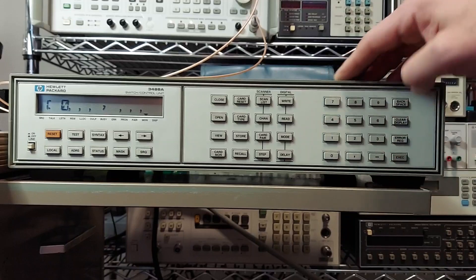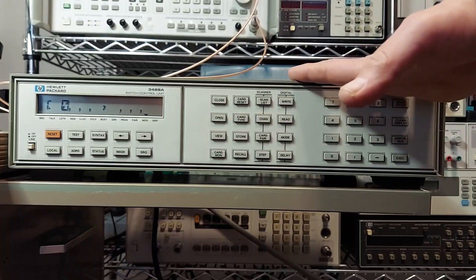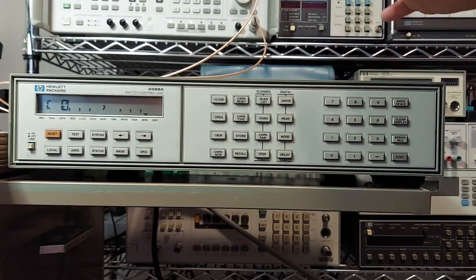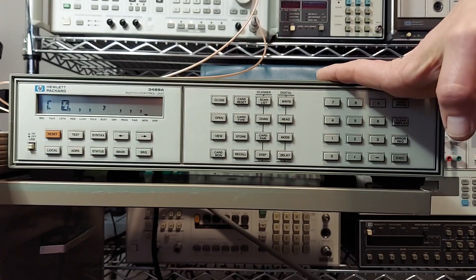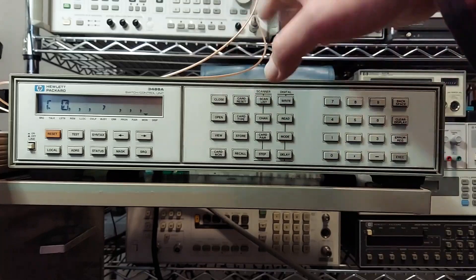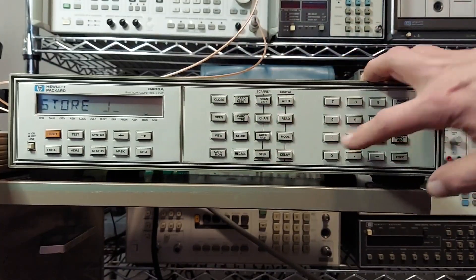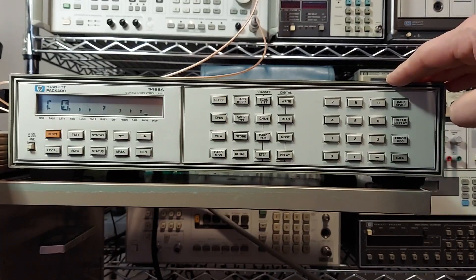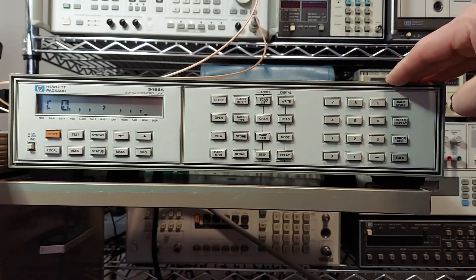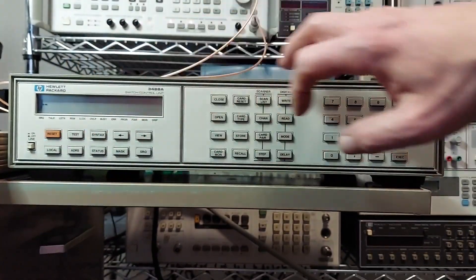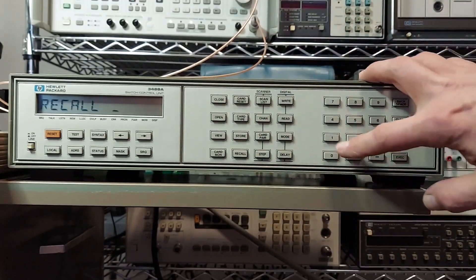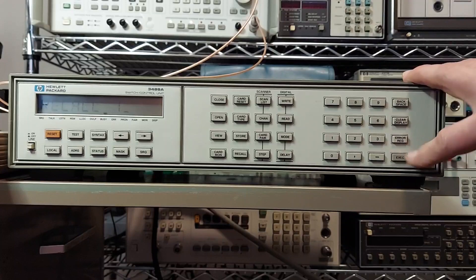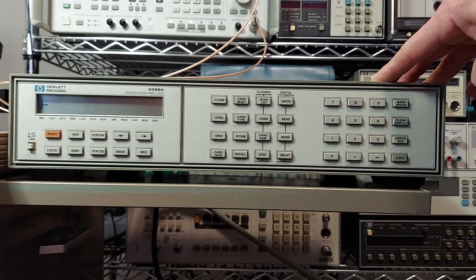You can also, if you have a complicated setup, you got multiple cards all hooked up, you got multiple relays closed, and you want to store that setup, well then you can store it. So we can take our setup here, press the store button, enter register one. And now that's stored. So if I wanted to come back to that, say we can do the reset here. And now I want to recall that setup, we can press the recall button, register one. And now the relays are all back into the same position that they were before.